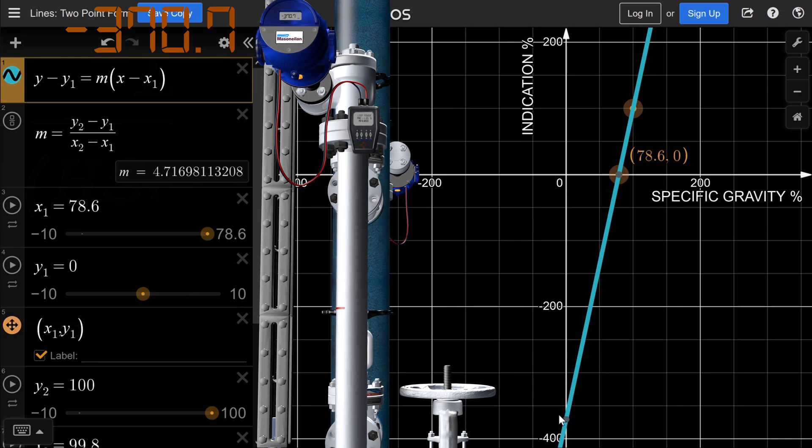The percentage indication still counts down, while the milliamps freeze at the minimum, which is 3.8, representing minus 1.25% at the DCS. That's why this check must be done in the field.